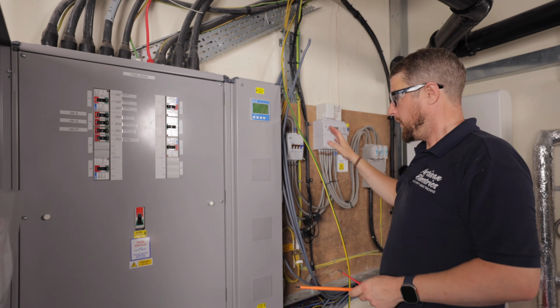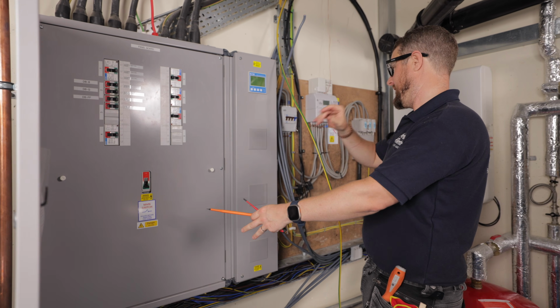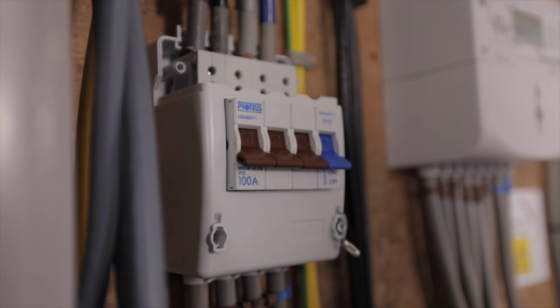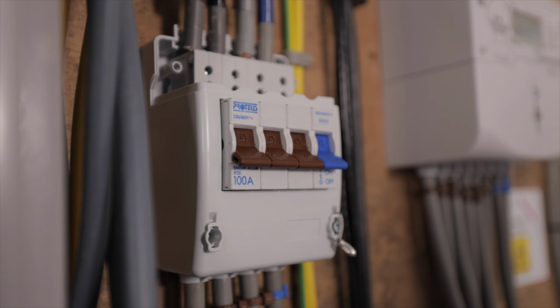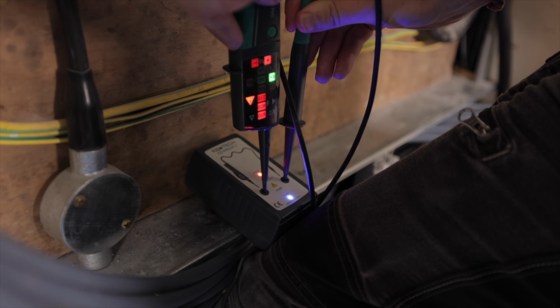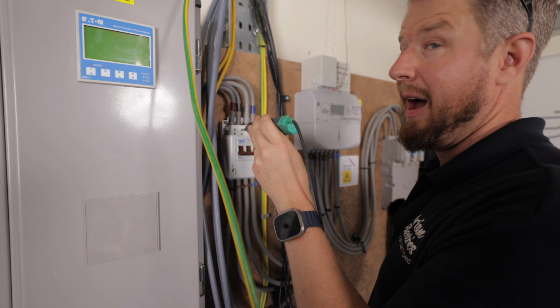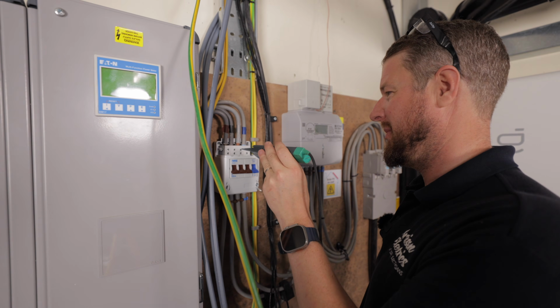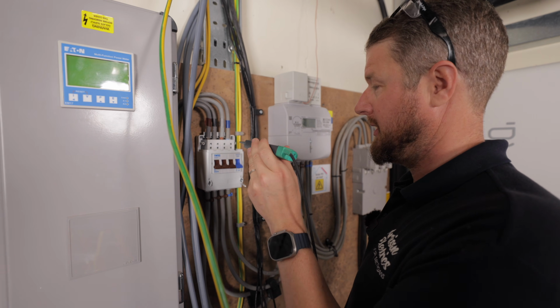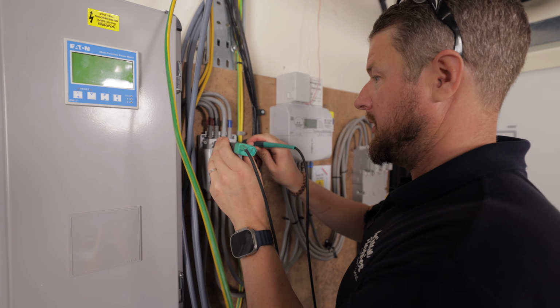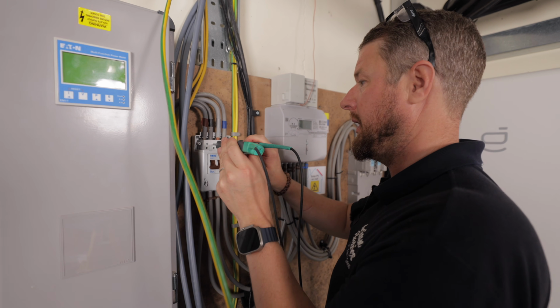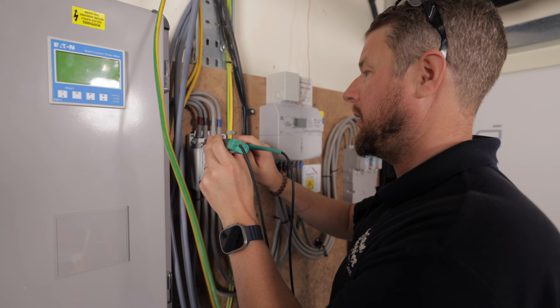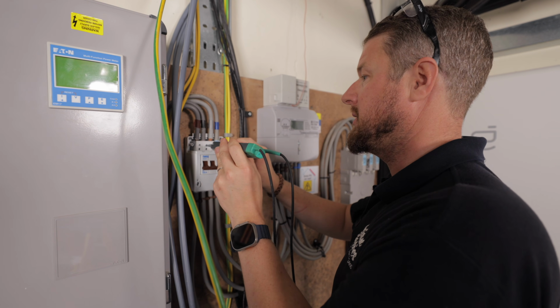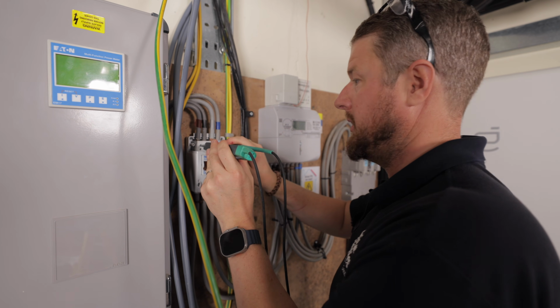However, we want it to be completely dead in there and safe to work, so we're going to turn this main isolator here off. So with 3-phase, there's a lot of different combinations that you need to test. Let me know how many combinations there are in the comments. L1, L2, L3 to earth and neutral to earth. Then we do neutral to L1, L2, L3, L1 to L3, L2 to L3, and then L1 to L2.